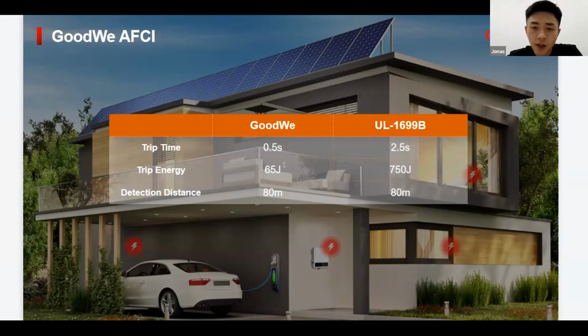And for the detection distance in the residential scenario, it can detect up to 80 meters. I think this is enough for the residential scenario, and this is also written in the UL requirements. For the AFCI, GoodWe is always developing and upgrading the software. Our current inverters use our second generation AFCI. This year, I didn't write it here, but we plan to upgrade it again, the third generation AFCI, perhaps in Q3 or Q4. At that time, all the parameters and performance will be improved, like the detection distance to be over 200 meters, and so on.